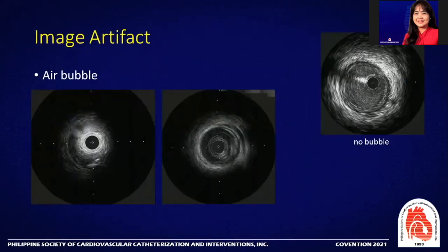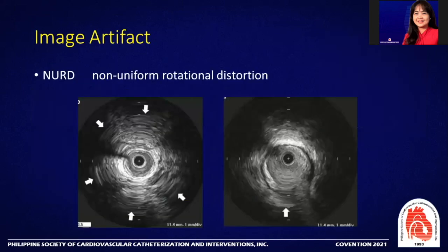Before I end, I think it is also important to show you some significant image artifacts that may give us inaccuracies in our image interpretation. This poor image here is due to an air bubble in the IVUS catheter. If you have this kind of poor image, it is advisable that you remove the catheter from the patient and adequately flush it again outside the patient. This is NURD, or non-uniform rotational distortion. It's brought about by bends in the catheter, especially when you pass through a tortuous lesion, or it could be due to a tight hemostasis valve.